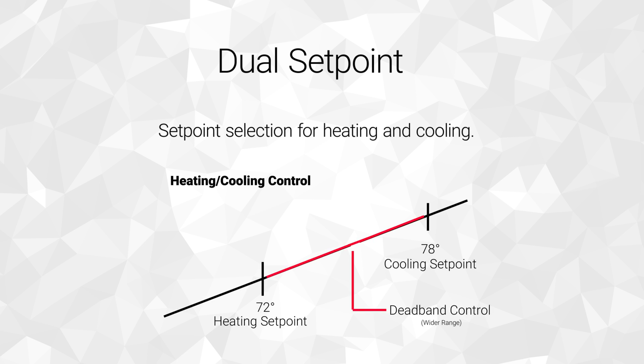Now let's look at a dual set point thermostat. As the name suggests, a dual set point thermostat has two distinct set points — one for heating and one for cooling. This allows for more control of the dead band, as the user now selects the temperatures required for the HVAC system to make a changeover from heating to cooling, or vice versa. As you can see, this allows for tighter control of the system, leading to energy savings and money in the facility owner's pocket.